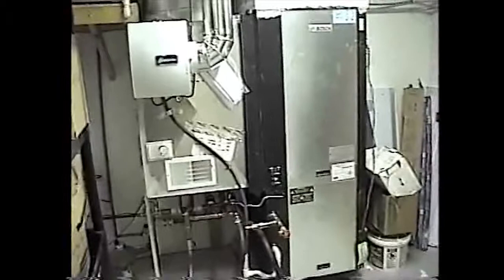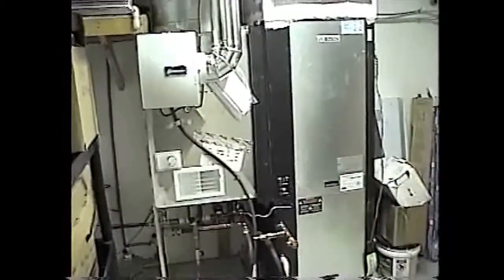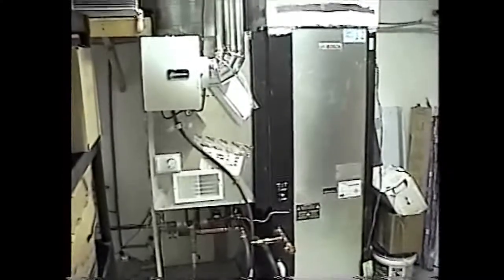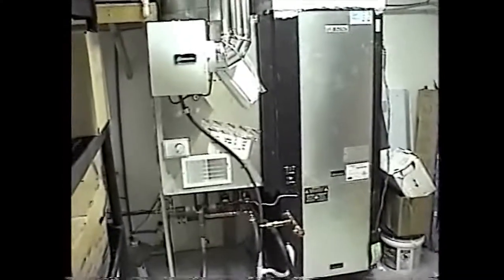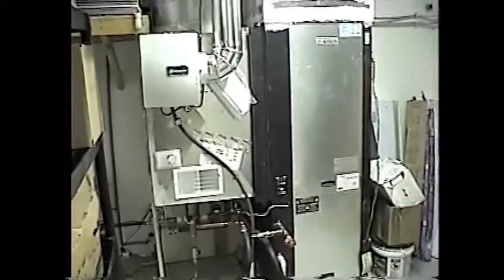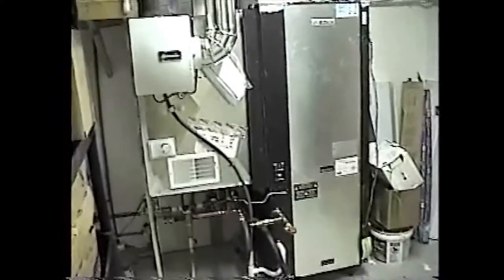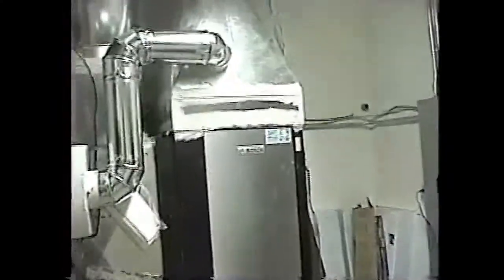What I was having a problem with was the fan in the on position ran the ECM motor at such a low speed that there were pockets in the space that just didn't condition properly. By adding on the control and with the magic that this little thing right here does, the place absolutely snapped to and is absolutely the same temperature. It's wonderful. The humidity is under control now, and the people are very comfortable. There are no hot spots, no cold spots anymore. And that's the sensor that I'm showing you right there in the supply duct.